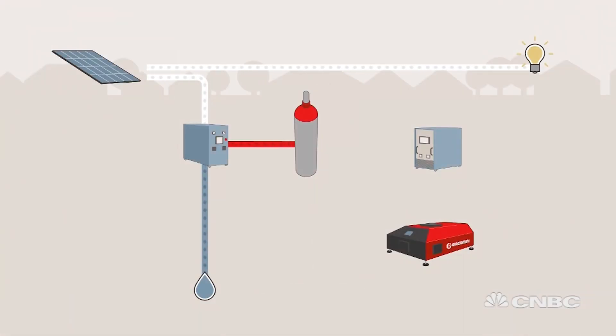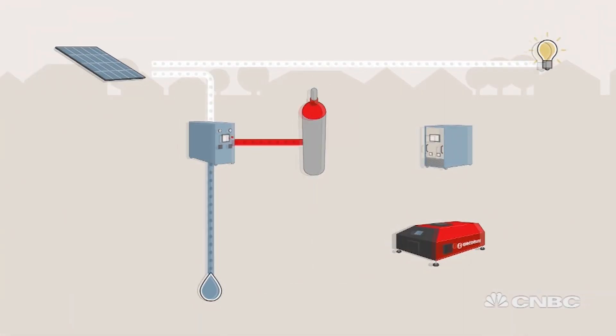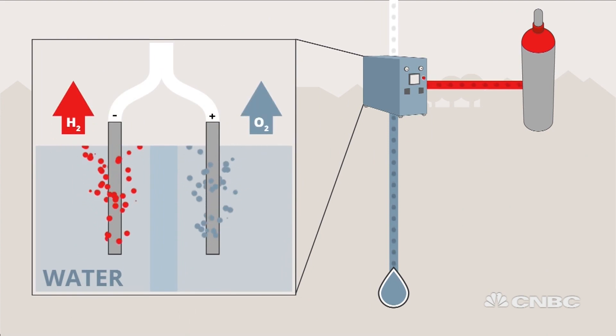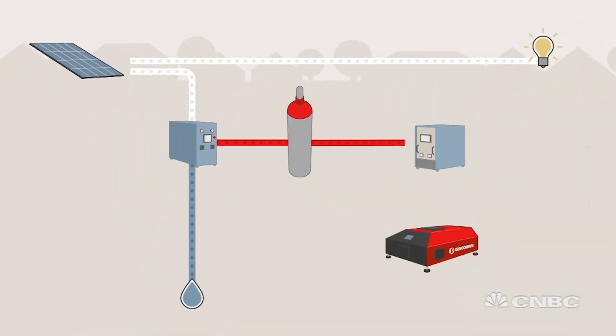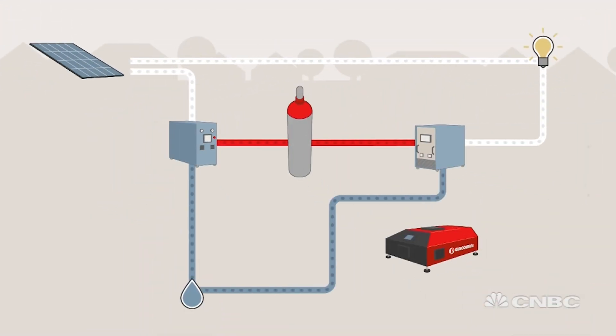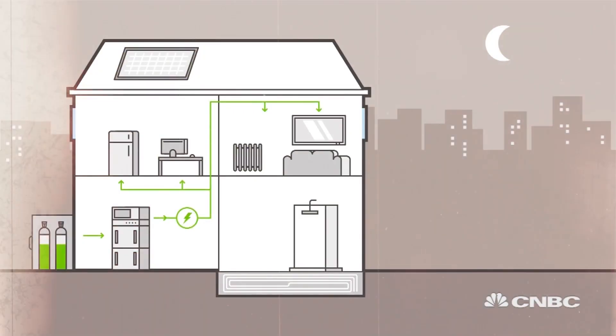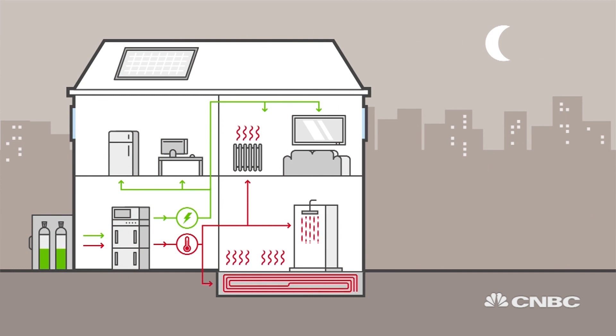The Solenko power box is based on three main components. One is a reversible fuel cell — electricity splits water into hydrogen and oxygen, and the same cell can later use the hydrogen to produce electricity and heat. It also has a catalytic boiler: fueled with hydrogen, it produces extra heat, and of course we also have a water storage tank in order to provide heat for sanitary applications.